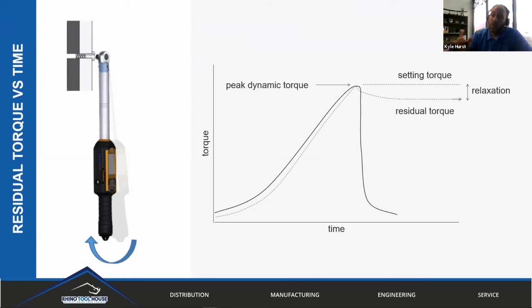To Ben's point before, what we would do to calibrate a tool is literally what we were just describing. When you calibrate a DC electric transducer, you put a secondary rotary digital transducer on the front of that tool, between the head of the tool and the fastening. We're comparing the result of the master transducer to the result of the control, the tool, and saying those must be within some allowable limit. With a direct drive DC tool, we'd say it has to be within 2%.